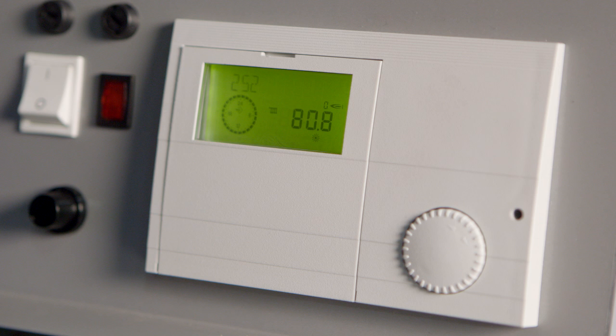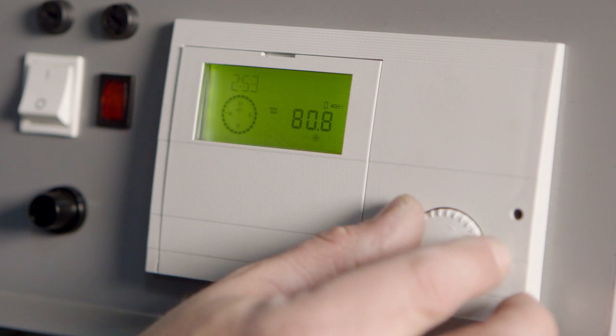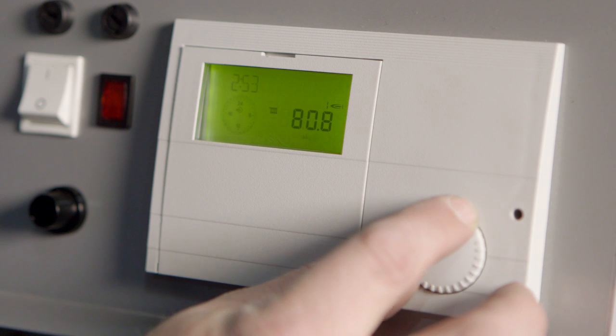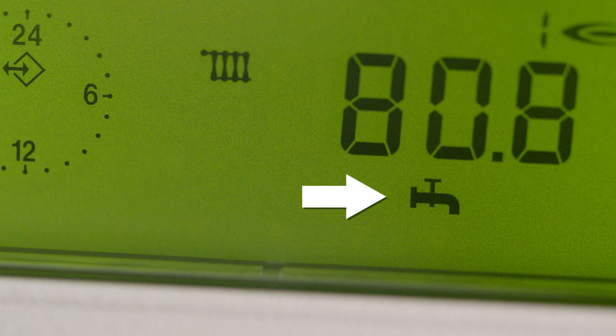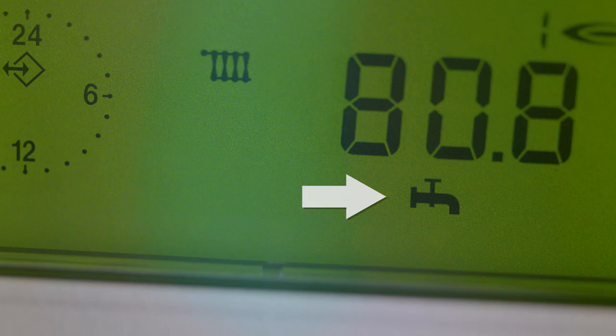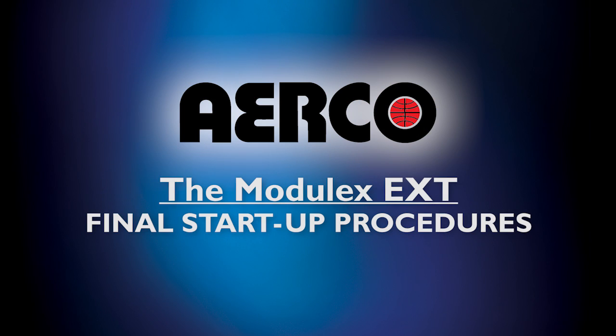If you're using your unit for domestic hot water and you want to shut down the heating side for the summer, then you can put your unit in summer mode. Do this by turning the wheel until this icon, resembling a faucet, appears as shown. Now that you've gone through all the other steps of starting your unit, it's time to show you the final startup procedures.